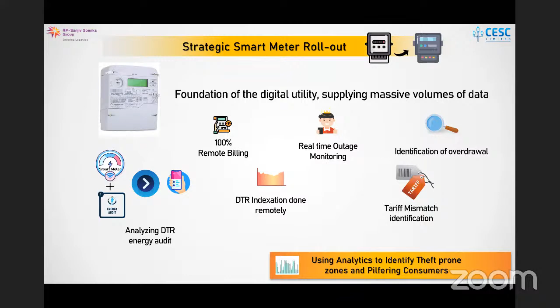Smart meters and HT AMR meters will automatically throw up outage alerts, which through proper IT enablement can be grouped into calls and directly flow to the complaint management system, to the vans, and then directly to the fuse man sets or fault restoration teams, who can then, with GIS enablement, directly go to the site and fix the problem.